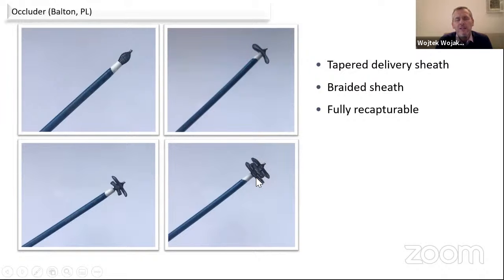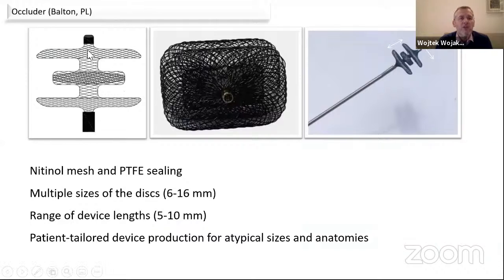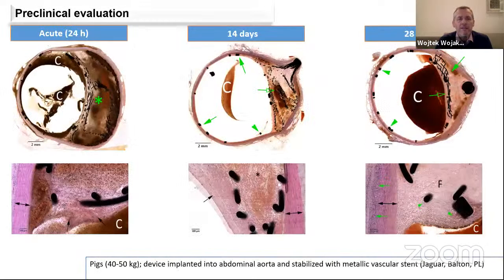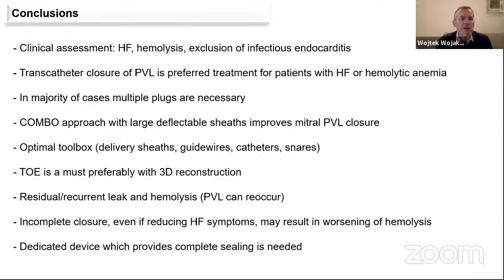It's a triple disc device, and it has a sealing fabric inside all 3 discs. So even if you stretch the middle module, it has a sealing, and even if there is some dog boning of the distal parts, it allows for a better sealing than one with only 2 layers of sealing fabric in the discs. This prototype was produced in different sizes, and it's quite easy for the company we work with to produce patient-tailored devices, sometimes very long, to approach the crescent-shaped long PVLs. And this device was tested in pathology in Canada with some good results in terms of biocompatibility, and it will enter the clinical study somewhere next year.